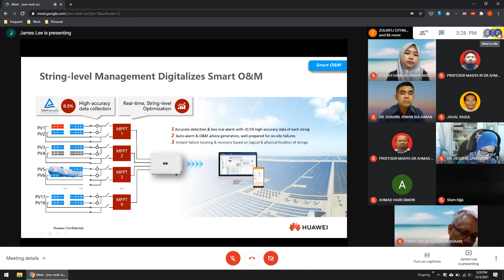And here is, I think, one of the key things. I know there are other IV curve scanners out there built into the inverter, but for us, we take pride in the fact that ours is usually TUV certified as well. TUV has verified that our IV curve has accurately detected up to 14 types of panel failure, and you can see here from some of the projects globally, and even here in Malaysia where we've tried to run it as well.